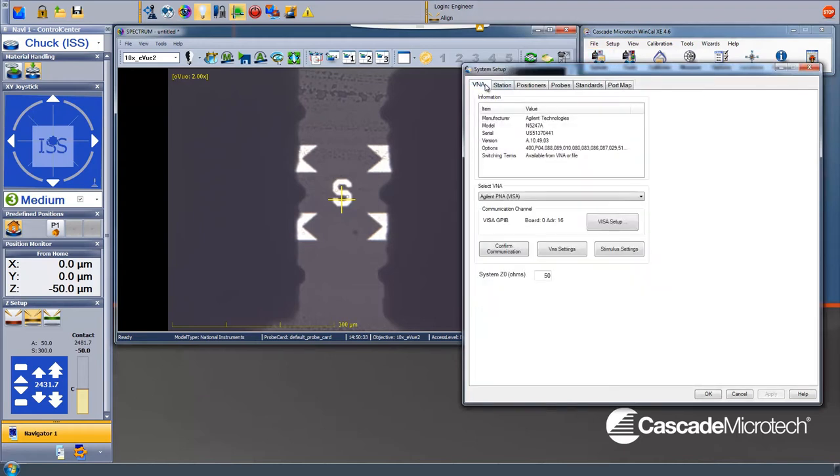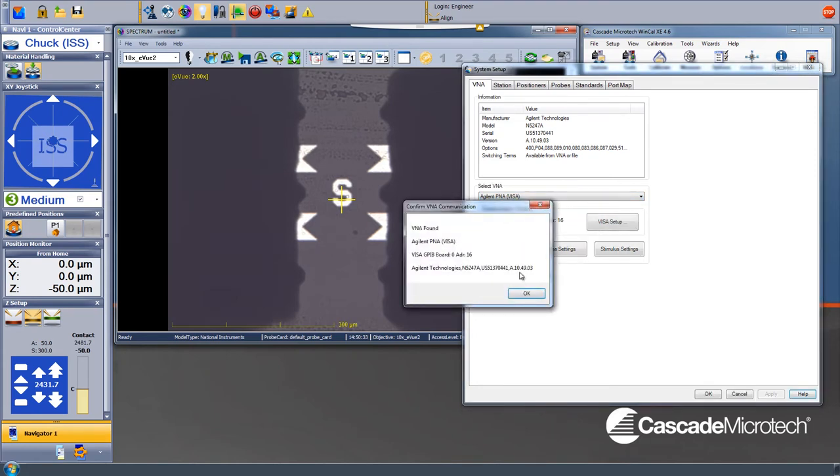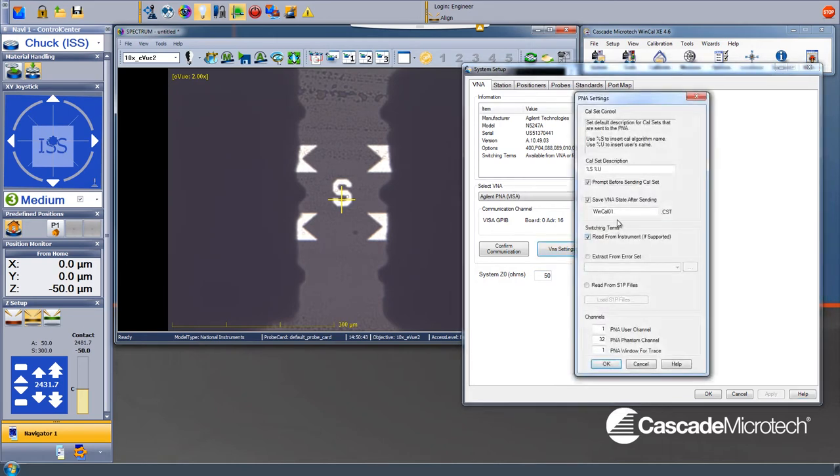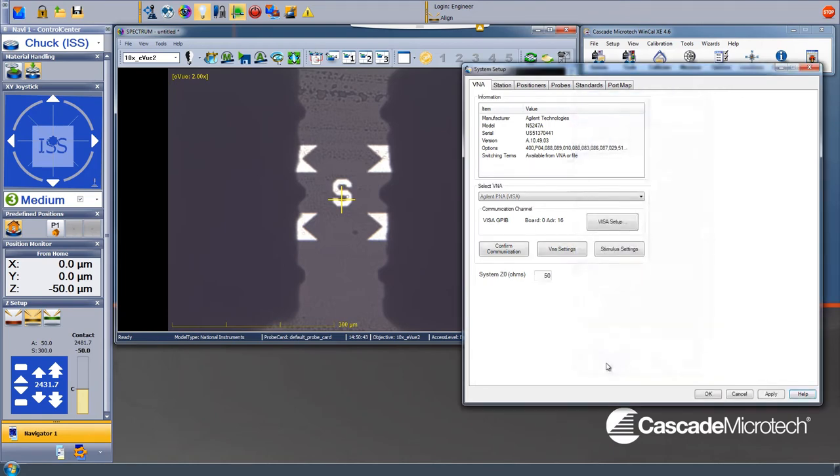First, we check GPIB connectivity to the PNA at address 16. No problems here. We double check PNA calibration file settings. Once the calibration is complete, it will store the results to the WinCal 01 calibration state table. We double check stimulus settings.